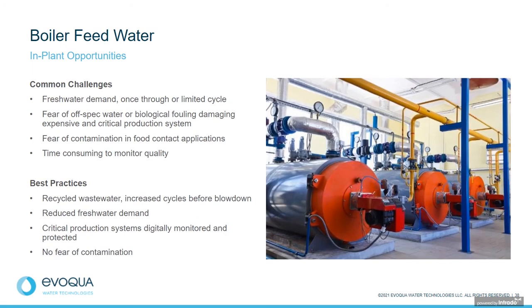The boiler, we're concerned about water quality, but we're concerned about protecting an asset that is often the heart of production. Even though a lot of low pressure boilers don't need RO quality water, often you can put an RO in front of them to give them better water quality to get more cycles out of that boiler feed water.